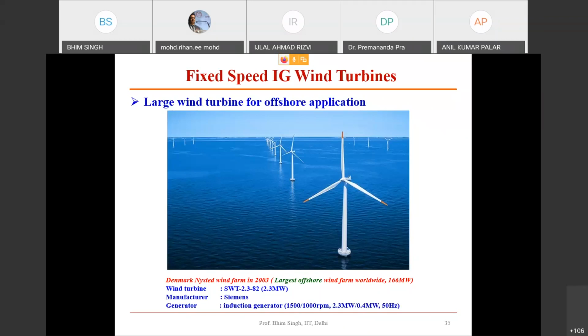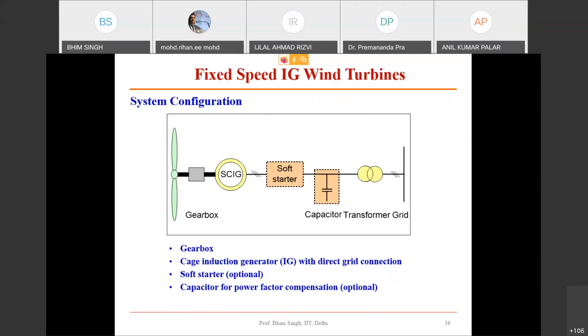Otherwise all machines use this. So Siemens is manufacturing the squirrel cage machine still, without any converter, with two machines on the same shaft. That is the configuration: a squirrel cage machine with a gear, a 3-stage gear, and then a soft starter with a capacitor bank connected at a suitable value, so that the excitation does not come from the grid.